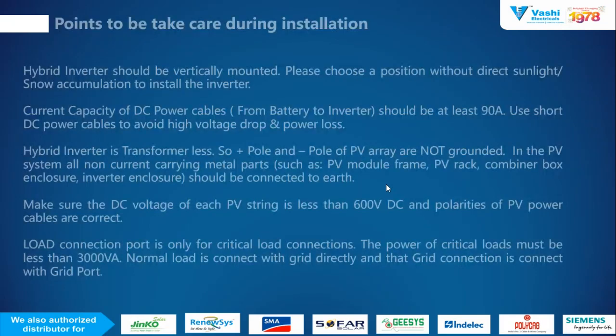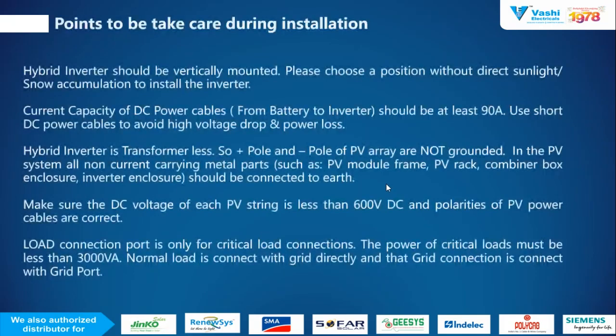Now, during the installation of the hybrid inverter, we have to take care of certain points. The hybrid inverter should always be mounted in the vertical direction. It should not be in direct contact with sunlight, otherwise its temperature will rise, and it will give the over temperature indication on the inverter. Also, the current carrying capacity of the DC cable should be at least 90 ampere, and its square mm size is mentioned in the manual for both AC and DC cable. You can easily get all this cable connection data in the manual.